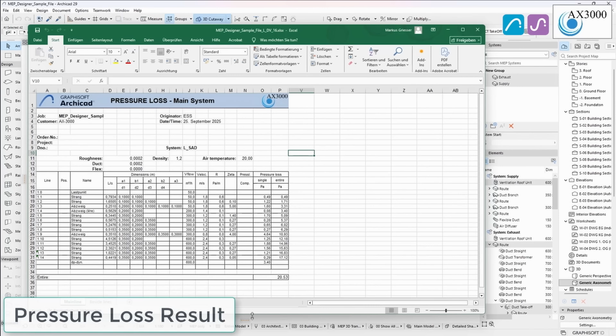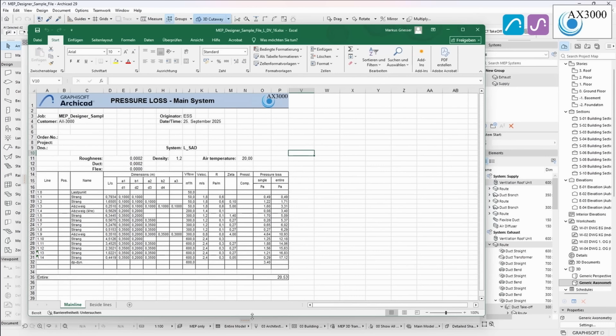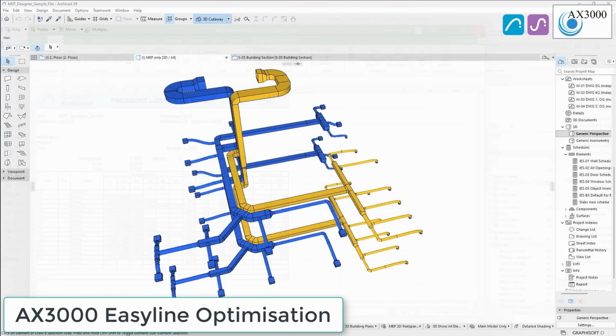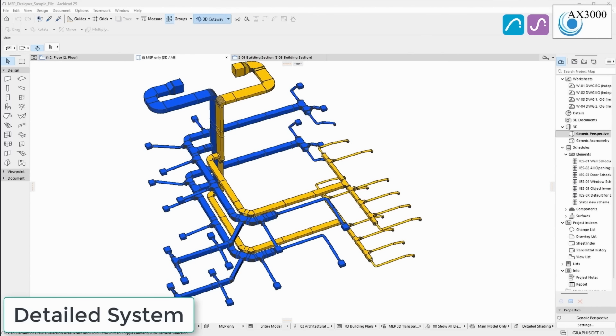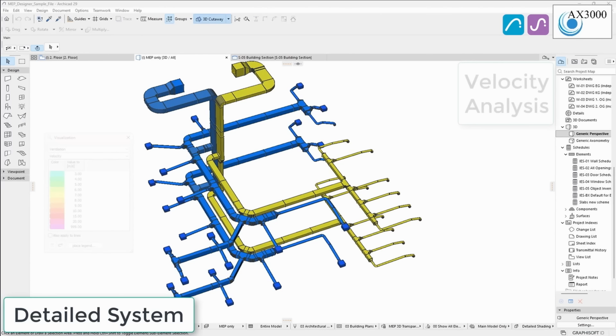These results are essential for accurately calculating the hydraulic balancing. With easy line adjustments, it is possible to change material on the duct system, and it also allows you to create a parts list. First, we need to check if airspeed and pressure loss are within limits. Color coding makes it easy to spot issues and highlight where bigger ducts are needed.